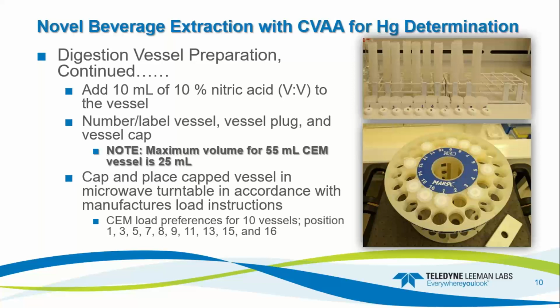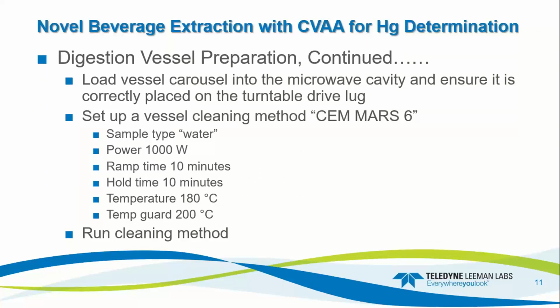Note that the maximum volume is 55 mL for the CEM vessel. The 55 mL CEM vessel is 25 mL. That's the max volume. Cap and place the vessel in the microwave turntable in accordance with the manufacturer's load instructions. The CEM load instructions for 10 vessels, which is what I'm using, is 1, 3, 5, 7, 8, 9, 11, 13, 15, and 16, and here it's depicted loaded into the turntable. And here is how I've set up the microwave vessels and labeled every part of that microwave vessel.